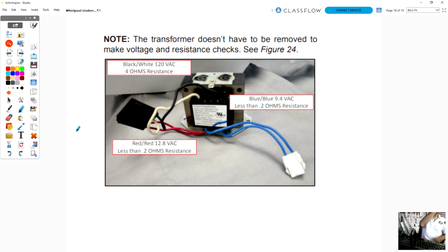Here's a picture of a transformer for the voltages. So we've got 120 volts coming in. That's our black and our white wires here. That's 120 volts coming into the transformer, and we have two voltages coming out, 9.4 and 12.8. So it doesn't put out 5. I was incorrect. So the board is what's stepping these voltages down for the sensors, which are asking for 5 volts or something. This transformer is separate from the main board and can be replaced individually.